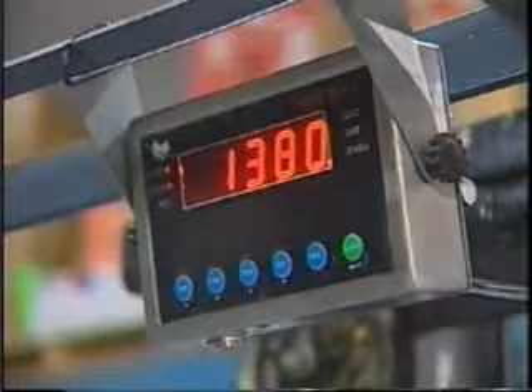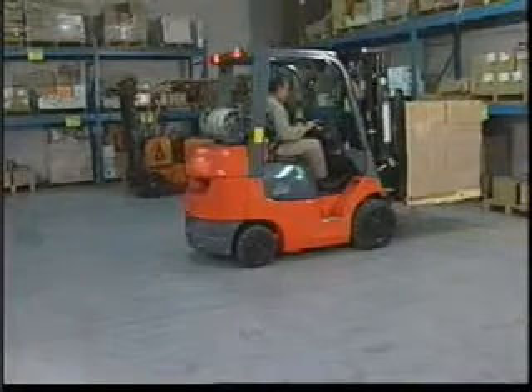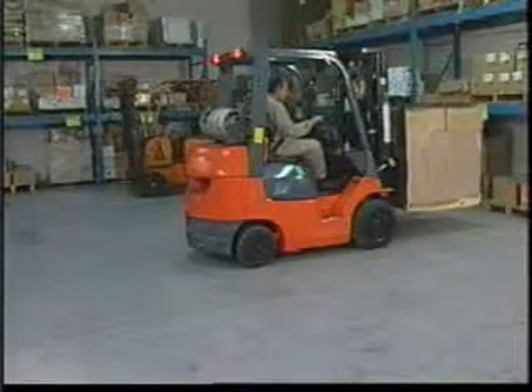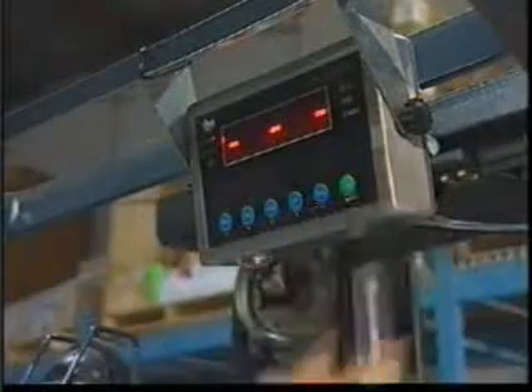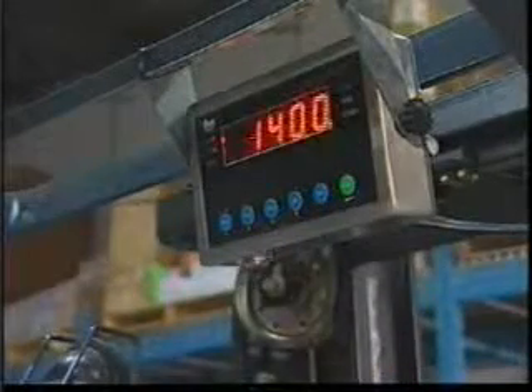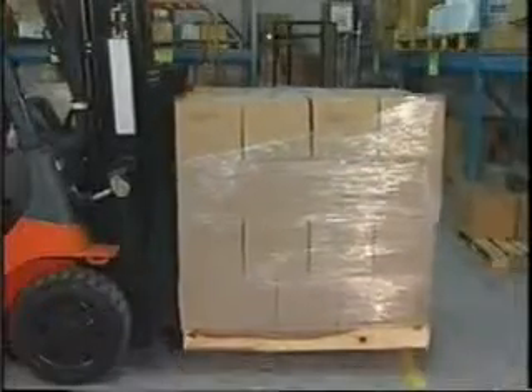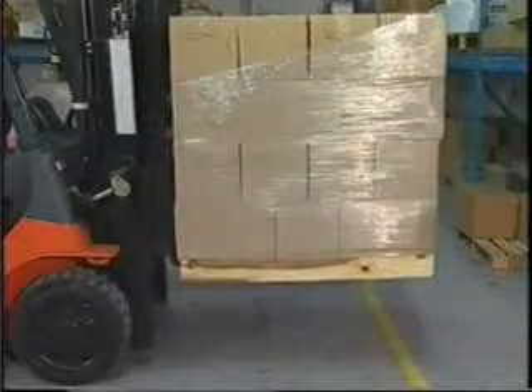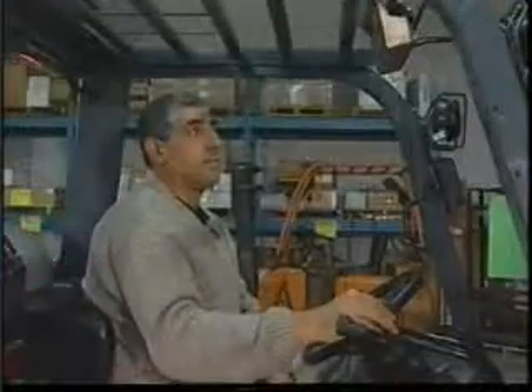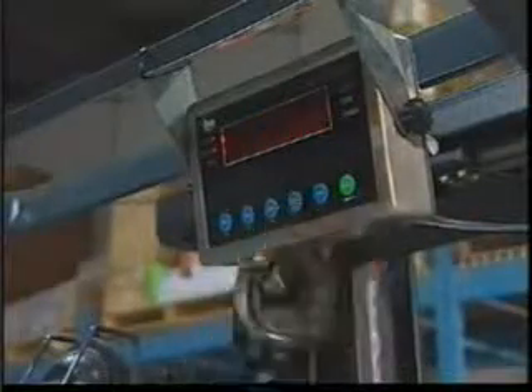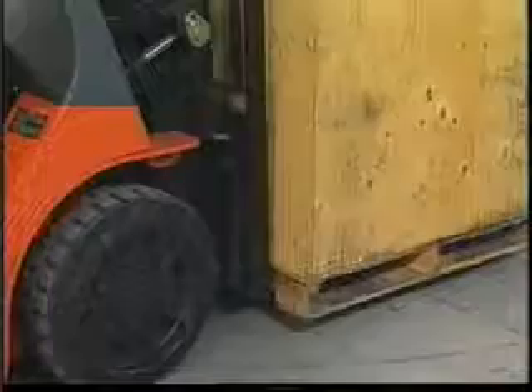The Safeweigh unit can add the total weight of any number of loads that you pick up. Simply perform the weigh cycle, and once the weight is indicated, press the add key to add this value to the total. Proceed to the next load and perform the weigh cycle again. Once the weight is indicated, press the add key to add this value to the total in memory. You can repeat this process as many times as necessary.